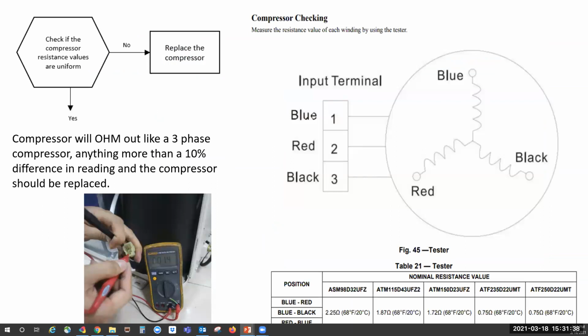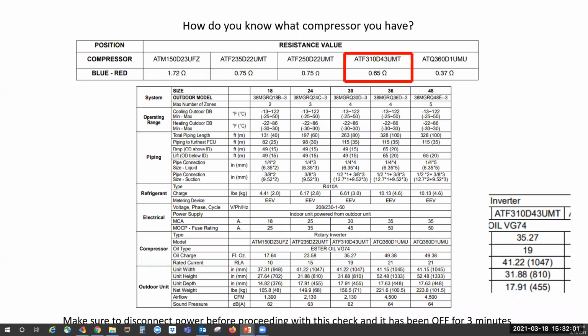For ohming out the compressors, you want to look in your service manual for the correct reading. Bear in mind, these compressors will ohm out very similar to a three-phase, meaning all three readings will be very close. If they're even off by 10%, this could be considered a problem. So when in doubt, you might check it a couple of times. In order to find out what your ohm reading is for the particular compressor you have, you're going to go here to find out what your model is.